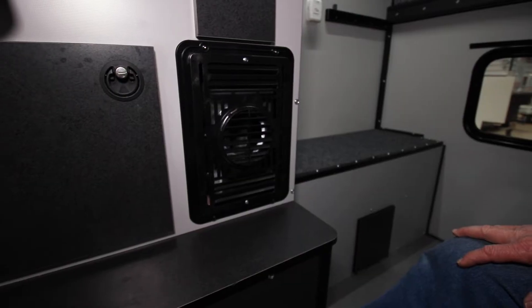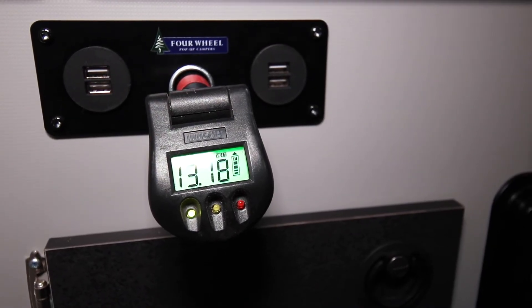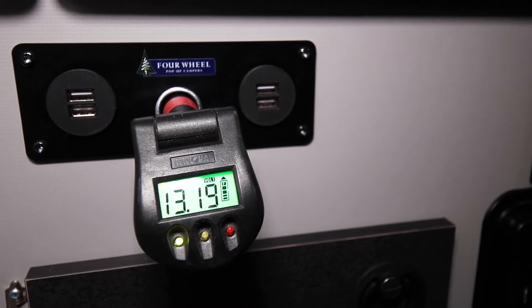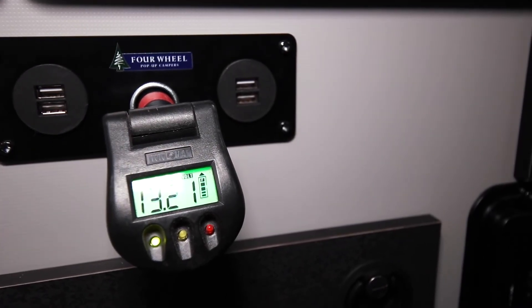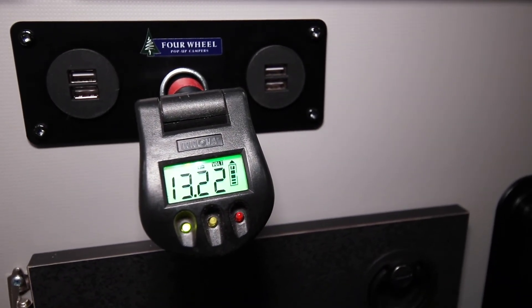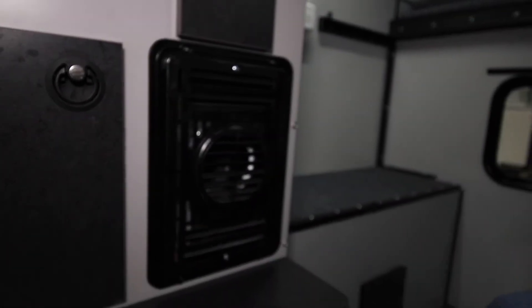We put the battery on a charger. You can see now we're on green — we've got a full 13.18 volts coming in instead of 11.9 volts; we're at 13.2 volts with a full charge coming in. This will allow the fan in the furnace to run faster and most likely ignite the furnace. For demonstration purposes, I'm kind of hoping the furnace won't light so I can show you how to check the sail switch. I'm going to go ahead and turn the thermostat back on — the fan kicks up and I can hear it running a little bit faster.